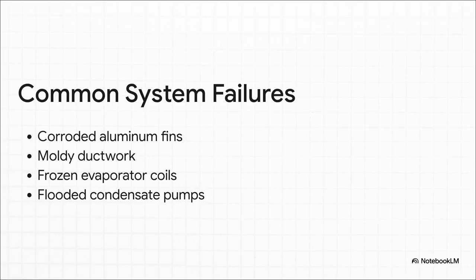The salt spray literally eats the aluminum condenser fins, blocking airflow and eventually killing the compressor completely. And that constant humidity we talked about, it breeds mold right inside your ductwork and air handlers. We also constantly see frozen evaporator coils because that restricted airflow causes the whole system to ice over. And finally, all that excess moisture overworks your condensate pumps until they just give out, completely flooding the area around your unit.